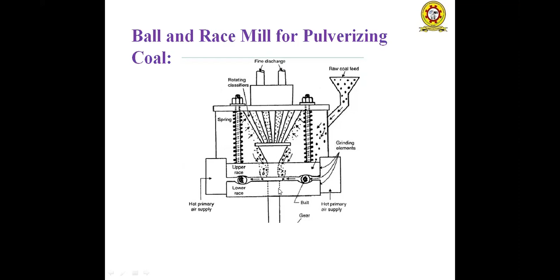For grinding, we also need an additional supply of air. So hot primary air should be supplied from these 2 chambers. There are 2 races, the upper race and the lower race. From the upper race, the fine particles are discharged. From the lower race, the heavier particles are recycled back to the raw coal feed.